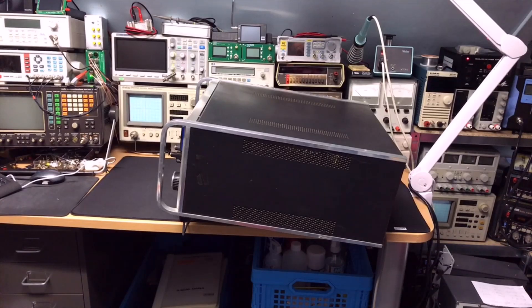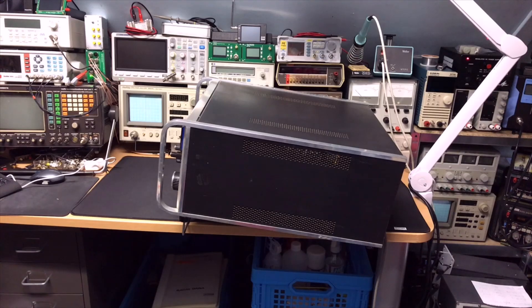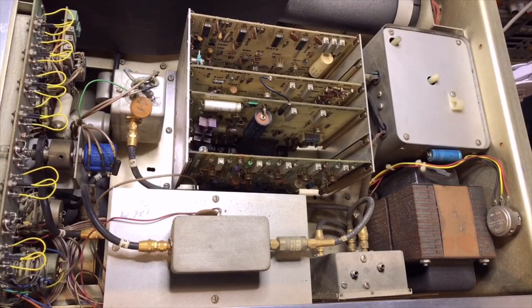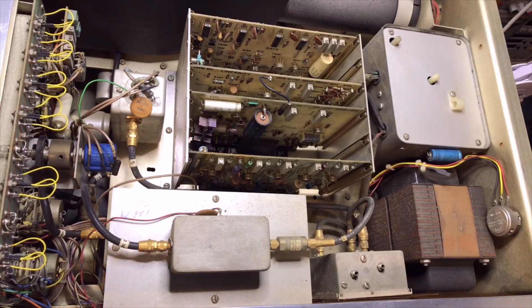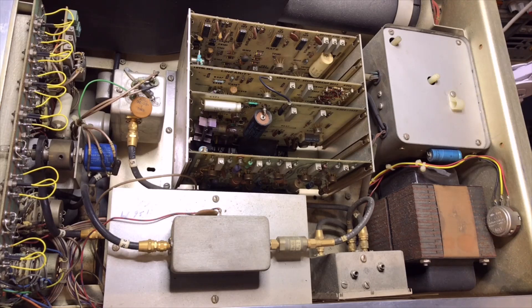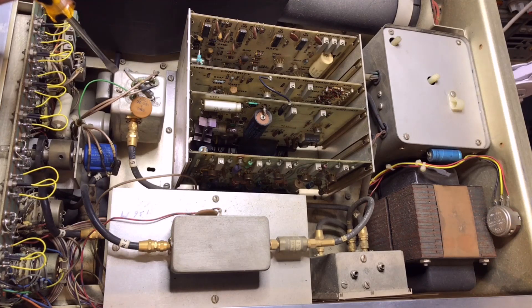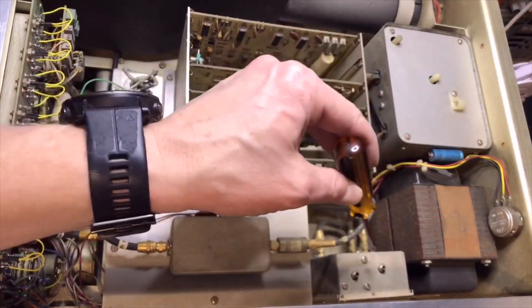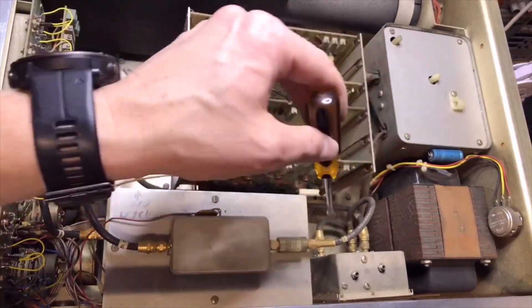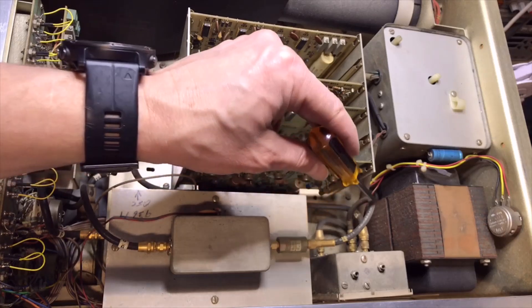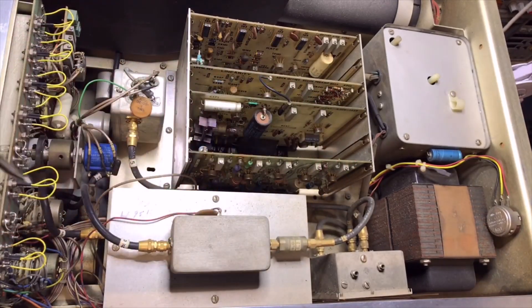As you can see, now it's on my bench and it is huge, it is really really big. But I will try to take the cover off and then we have to look inside. Look at this, talking about old technology. But I think it's easier to see how it kind of works because then you see, okay, this is probably the oscillator, and it goes in here. This is a box with three inputs or three connections. The oscillator is here, so then it's probably mixed here. In the bottom here comes the cable from the front through the attenuator. So then the mixed signal goes in here, goes there, that goes to the attenuator of the IF section.